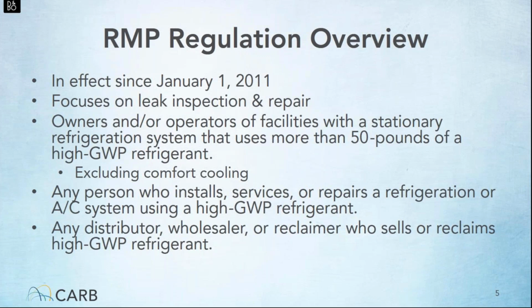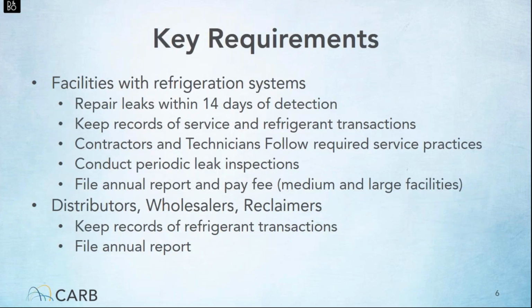The RMP rule applies not just to stationary non-residential facilities with refrigeration systems containing more than 50 pounds, but it also affects refrigeration distributors, wholesalers, and reclaimers, as well as technicians who service, install, and repair refrigeration systems or air conditioning equipment. Some of the key requirements for RMP have been in effect since January of 2011 and apply to all facilities of any size.